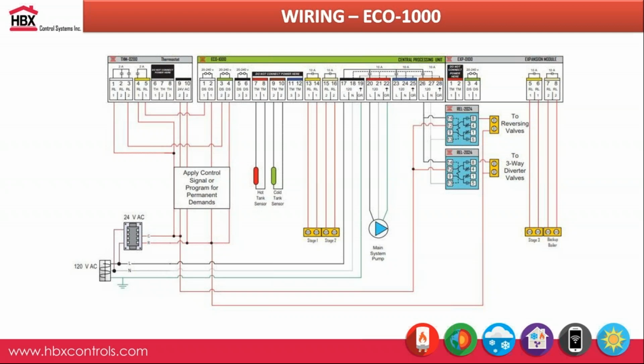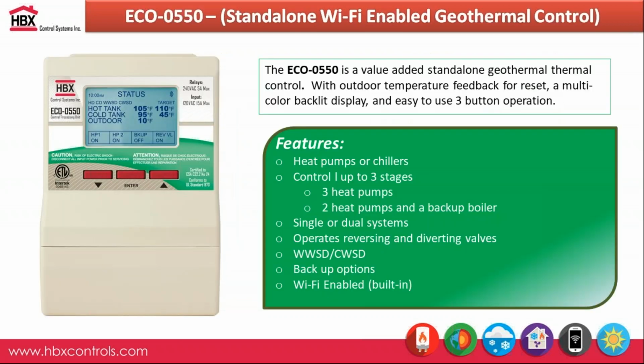The last relay on the Eco 1000, on pins 26, 27 and 28, is for a reversing valve. Since we do have line voltage there, just because this is the same manufacturing board that you use for our boiler controllers, you will need to add on a relay to accommodate if you are using a reversing or diverting valve with the 1000. So that's kind of the Eco 1000 in a nutshell.